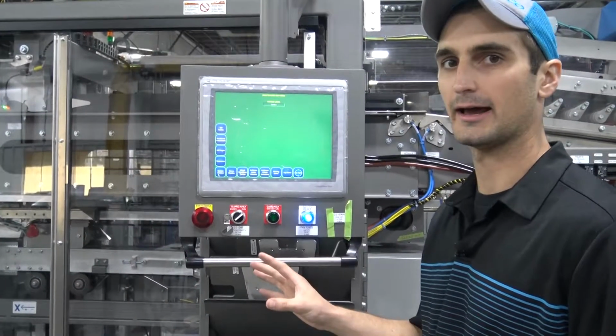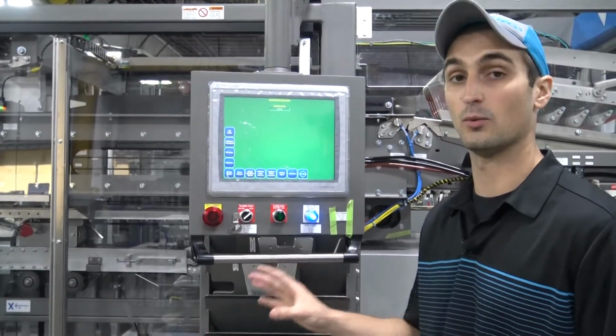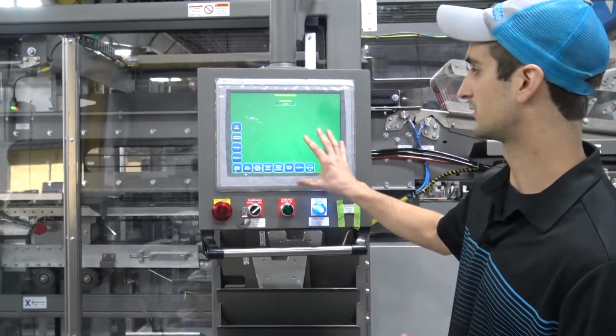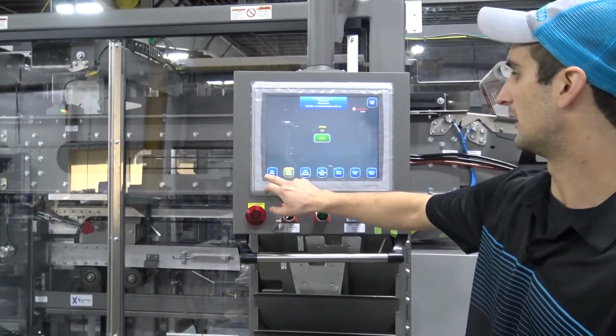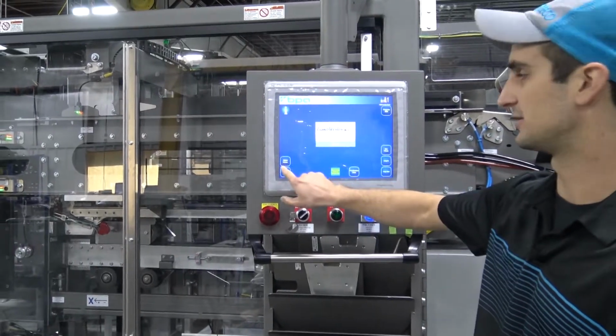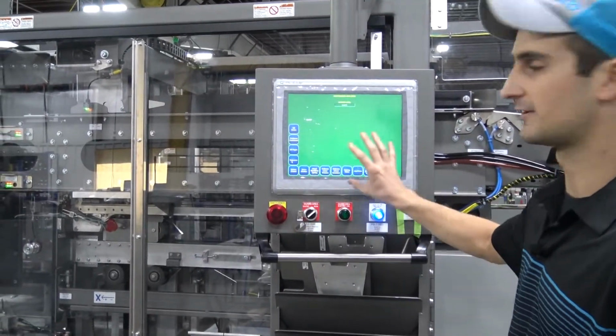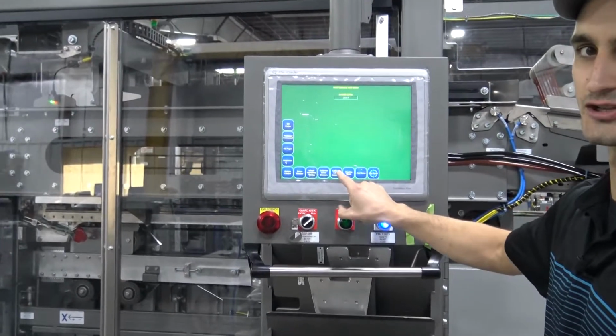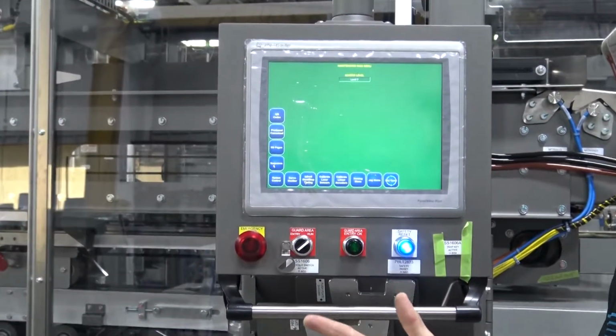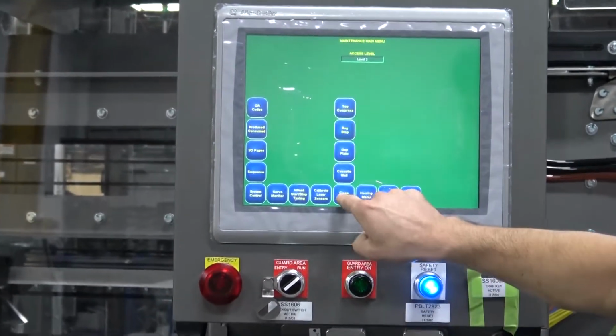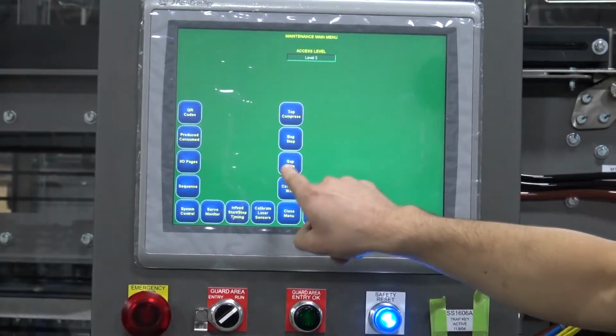We're going to demonstrate how to calibrate your cassette wall width. So I'm logged into the maintenance level. If I go to main menu and I go to the maintenance page, here are your maintenance functions, and I want to calibrate a linear actuator, the linear actuator that dictates the width of your cassette wall. So I pop that open, and then there's the cassette wall.